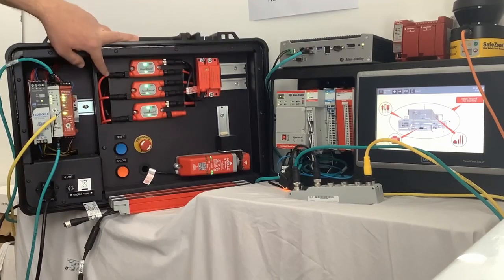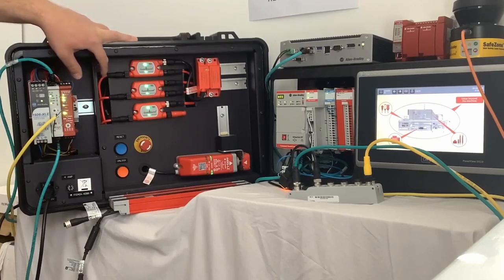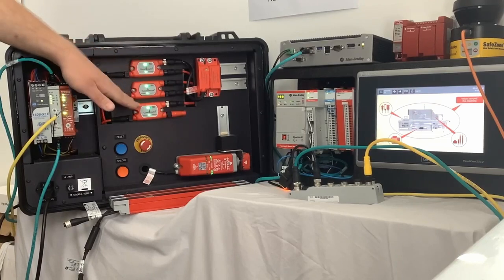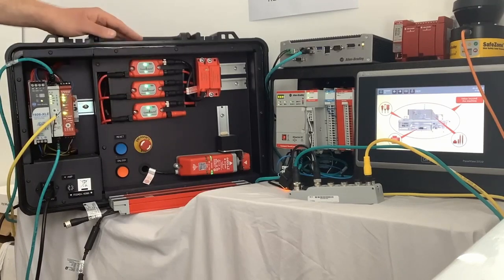The M12 cables come pre-made from ourselves. So you buy them, it's 30 centimeters up to 30 meters. So that is the maximum you can have between each tap. So 30 meters, 32 taps, you work it out. It's just shy of a kilometer.